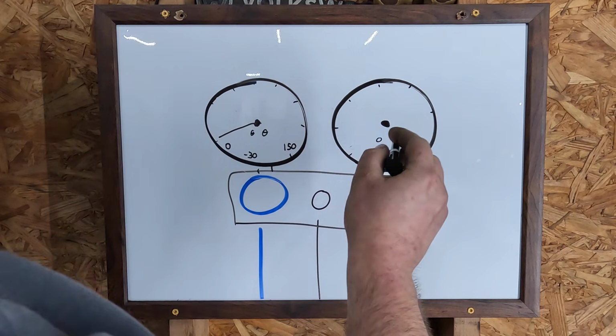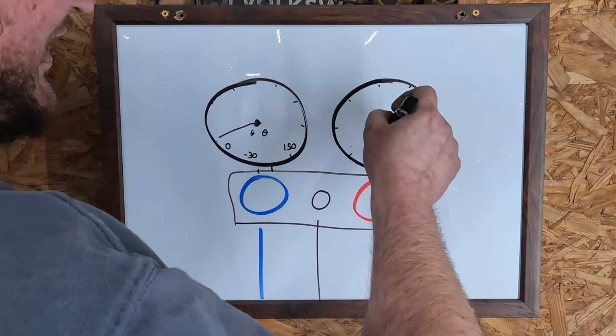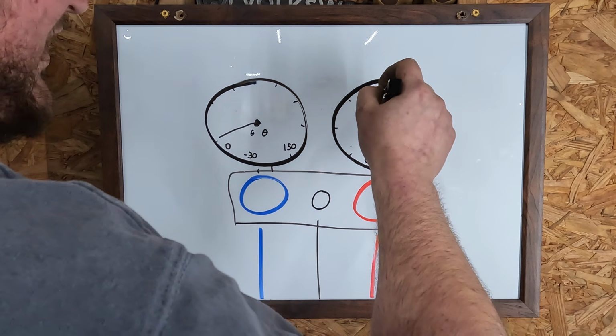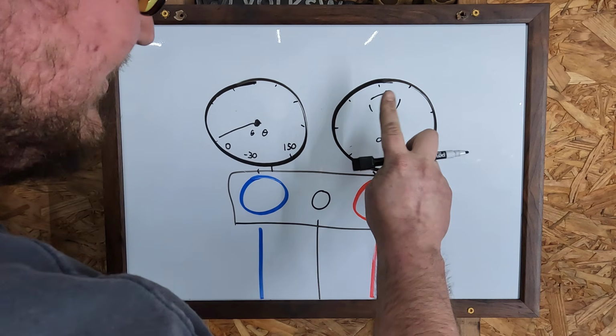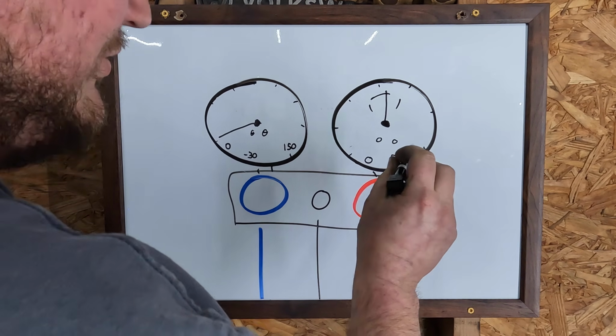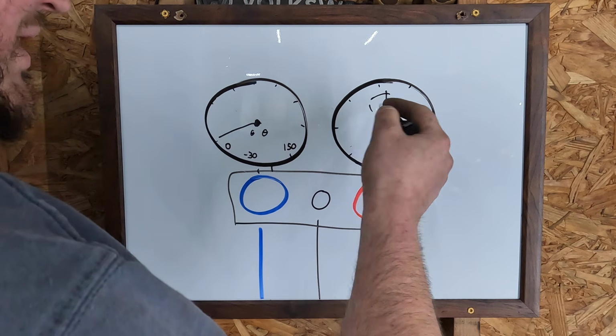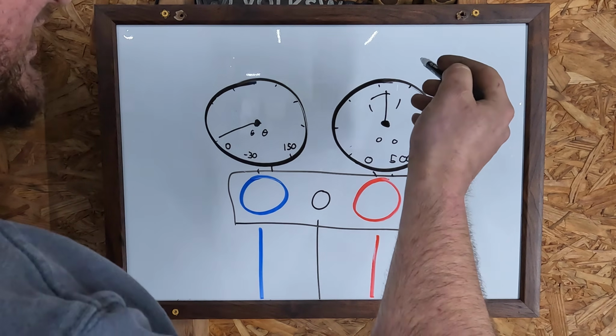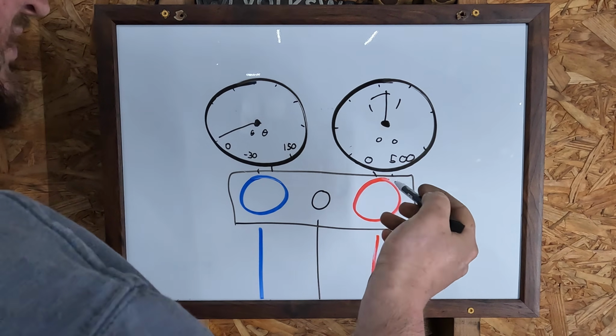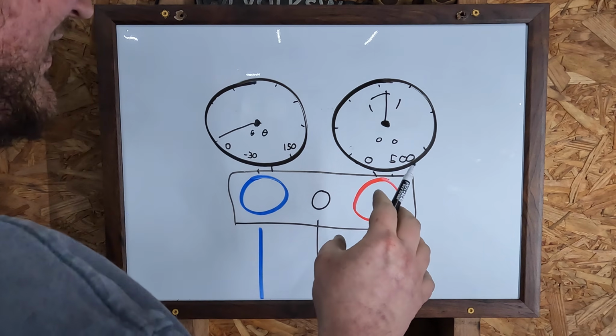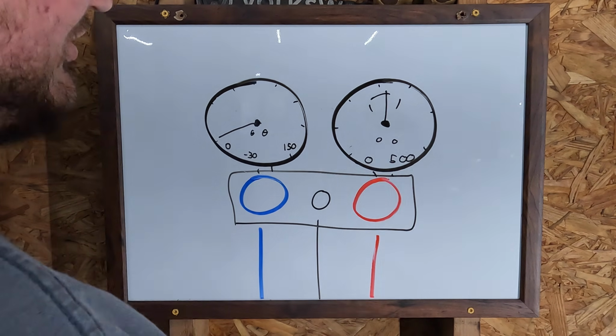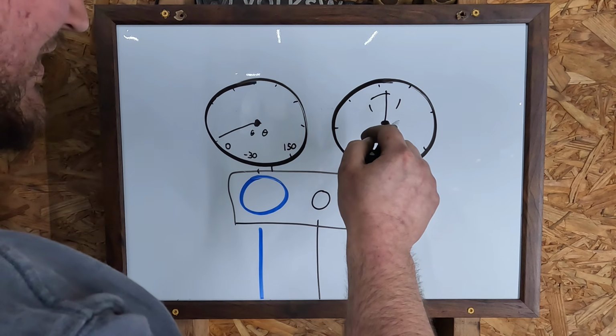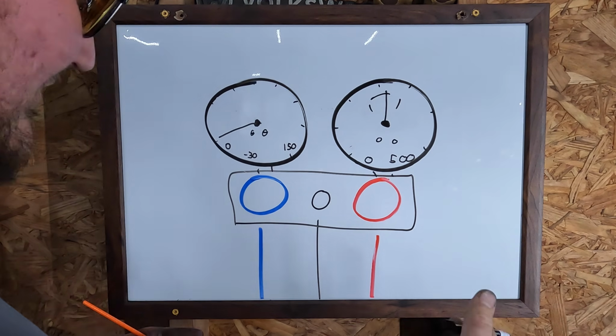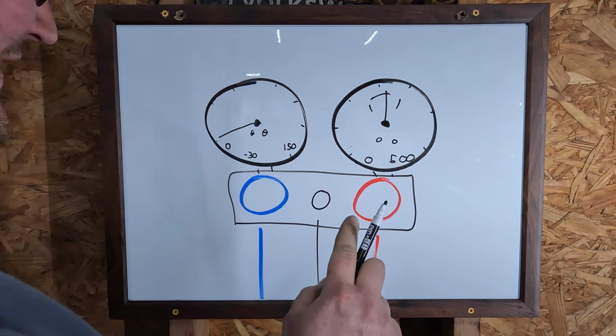Furthermore, the motion of the needles can also tell you stuff. If your high side needle is vibrating back and forth, it'll dance a little bit, but if it's really wagging back and forth, that could be indicative of maybe a dead cylinder in the compressor, a bad check valve in the compressor. But typically when compressors go bad, they go bad all at once. Also, an easy way to tell is if you drain the oil out of the compressor and of course there's glitter in it, that's no good.